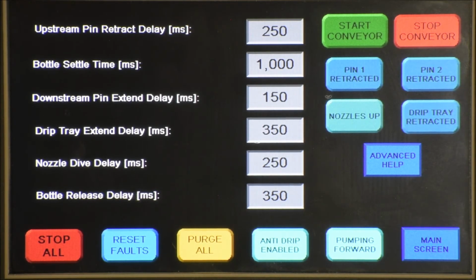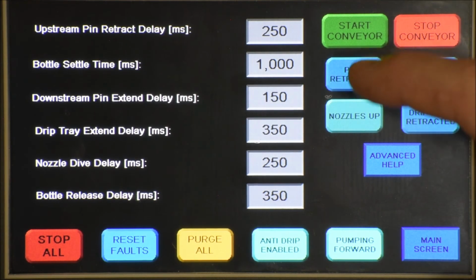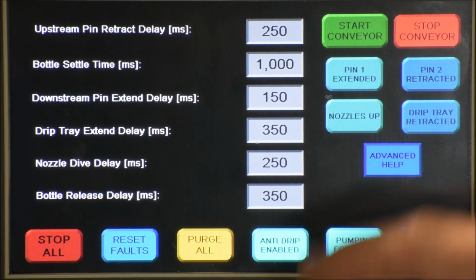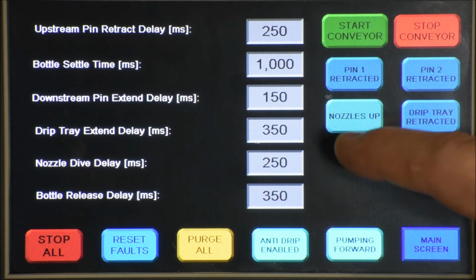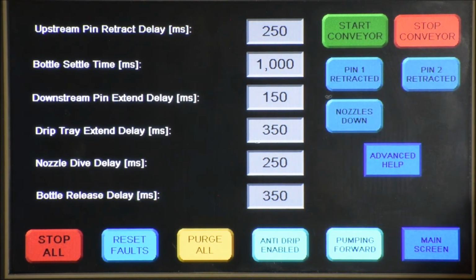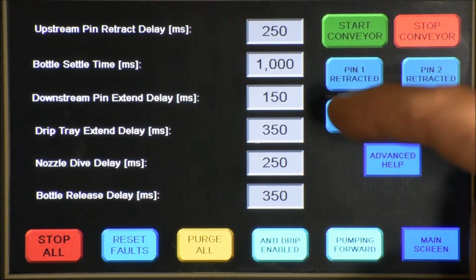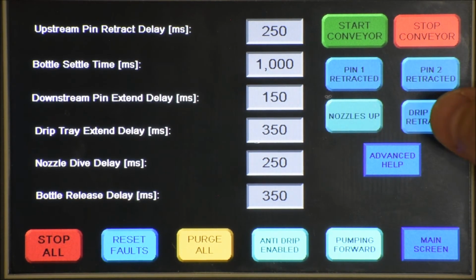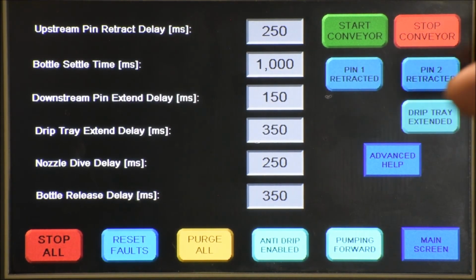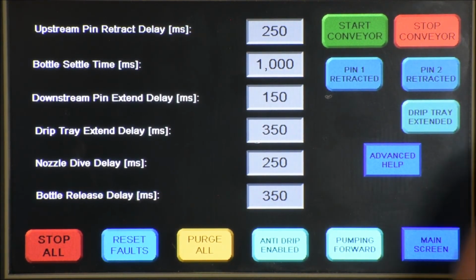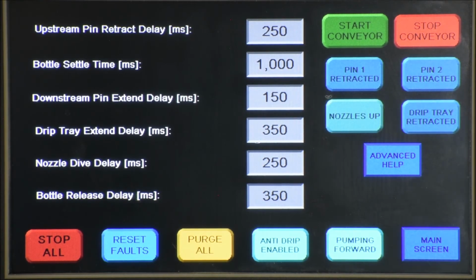Similar to the pump calibration menu, we've got all the buttons on each screen to manually actuate all the pins, the nozzles up and down. When the nozzles are down, you can't extend the drip tray or else they'll collide. So with the nozzles up, then you can extend your drip tray. If your drip tray is extended, you can't send the nozzles down because they would collide. So once we retract the drip tray, then we can move our nozzles up and down.